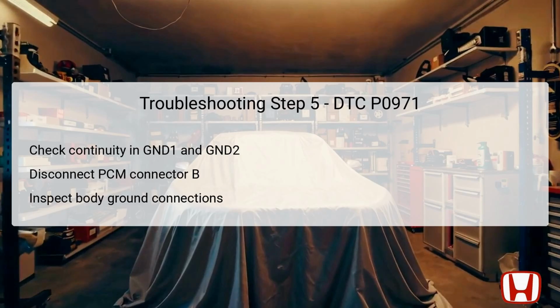If there is continuity between the connections, it indicates that the grounds are intact and you can continue troubleshooting. However, if no continuity exists, repair efforts must be directed at both the GND1 and GND2 wires between the PCM and body ground to ensure a reliable electrical grounding system for all respective components.